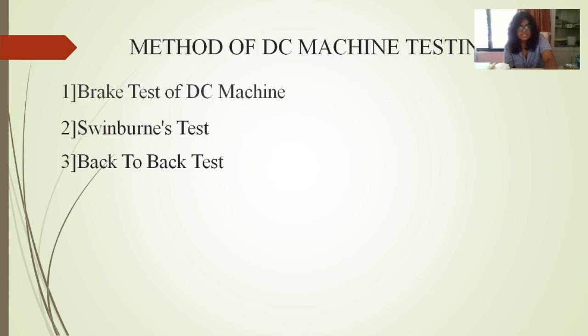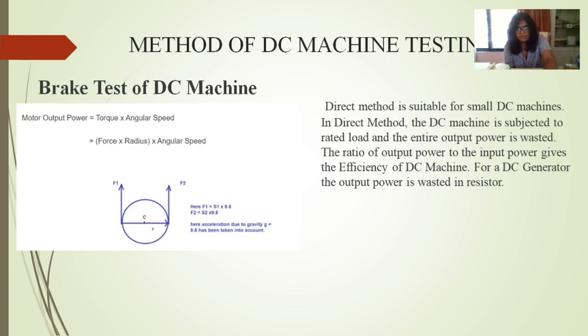The methods of DC machine testing. The first is brake test. The second is Swinburne test. And the third is back-to-back test. So the brake test, its direct method is suitable for DC machine. In direct method, the DC machine is subjected to rated load and the entire output power is wasted. The ratio of output power to input power gives the efficiency.